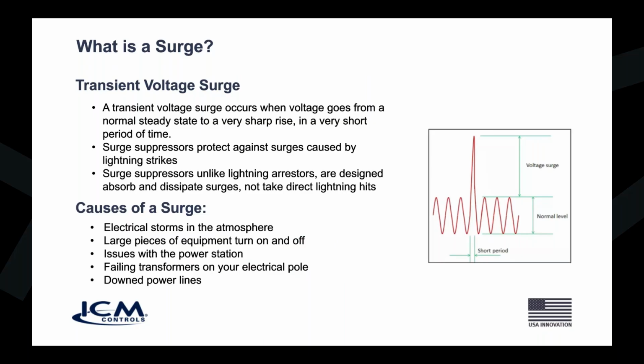You could have issues with the power station. The power station might have a problem where you got fluctuating voltage or brownouts, and then an immediate loss of power and then on with power and then off. We've all seen that happen from time to time. Failing transformers on your pole. Those can go bad and start failing. And when they fail, they create a lot of terrible surges. And you can have in storms and so forth, downed power lines that are just acting very erratically and shorting to ground, and all kinds of weird problems going on there as well that can create these surges.